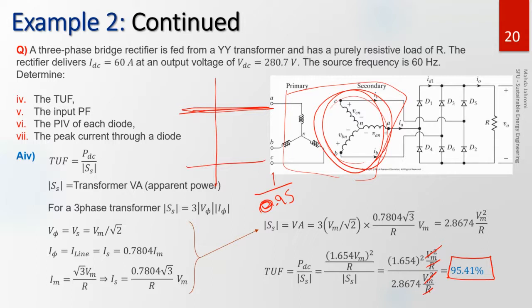So what's 1 over 95%? About 5%. So whatever is the power rating, you have to add at least another 5% to it. Usually we do much more over-design than this, so we might add 25 or 50% to the power rating, just to be on the safe side.